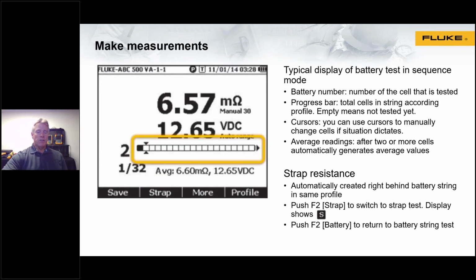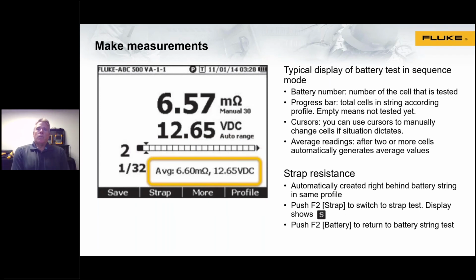What's highlighted there is the number string, so you can easily see which batteries you've already tested and which ones have yet to be tested. Something that's pretty useful, and we'll come to this when we get to the software, is that it's handy to know what an average reading is in the string. The tester can provide that information after the fact. If you don't yet know what good looks like, one of the techniques is to take the average of all the cells or batteries in the string and use that average value as a baseline. So this automates that process for you.